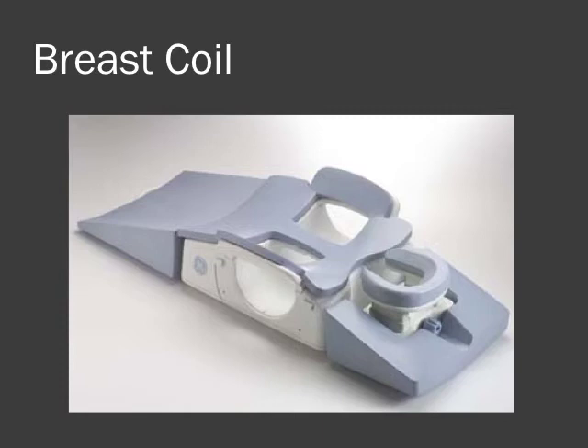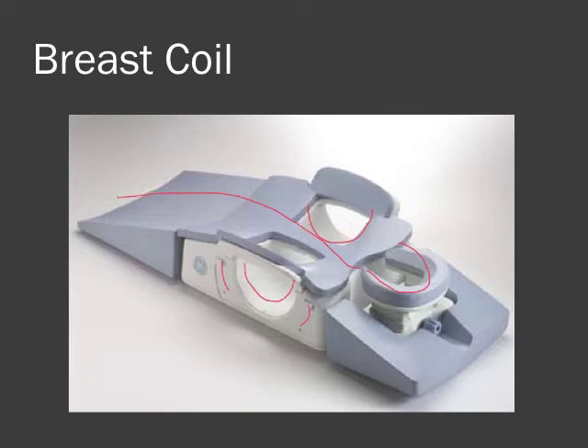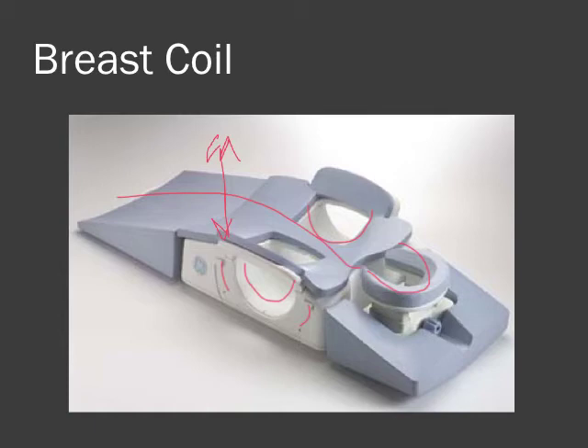Here is one example of a typical breast coil. The patient lies along here with her face down as if on a massage table, and her breasts are dependent within the holes, with the coils built into the hardware surrounding the breasts. This coil fits on top of the usual MR table. Its limitations include patient size — there needs to be sufficient distance between her back and the top of the magnet. This effectively limits patient size to around 220 pounds, and breast size to about a double-D or possibly E cup before significant artifact occurs.